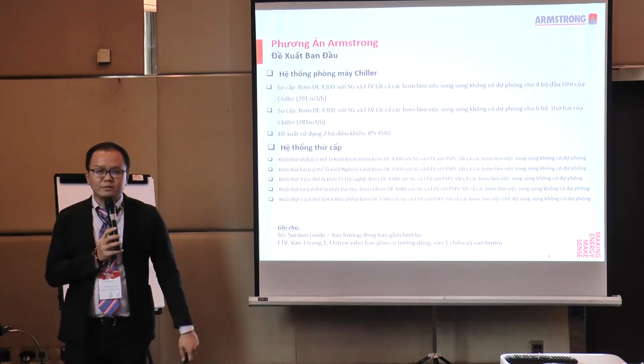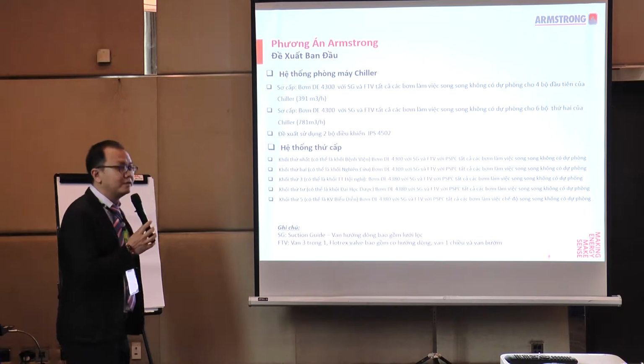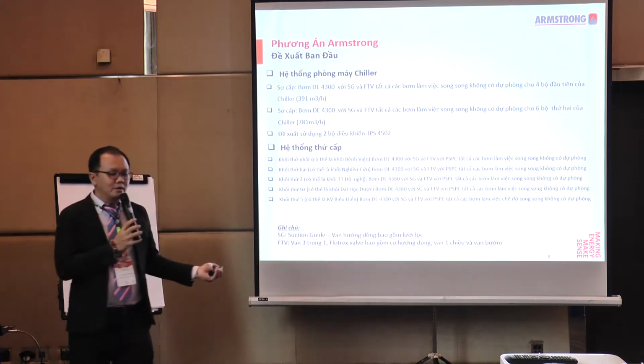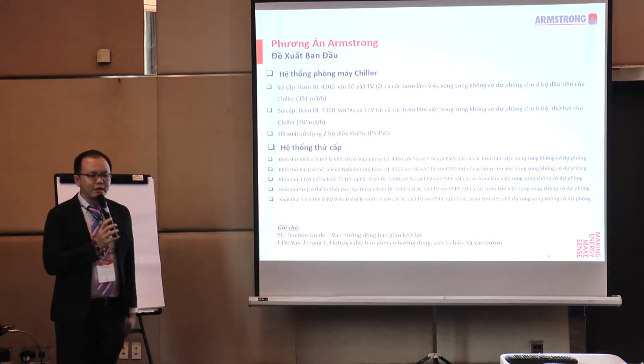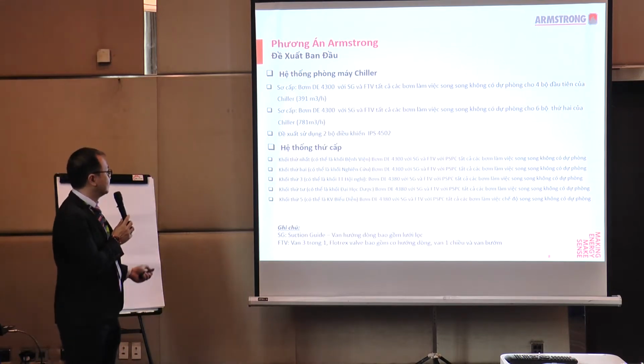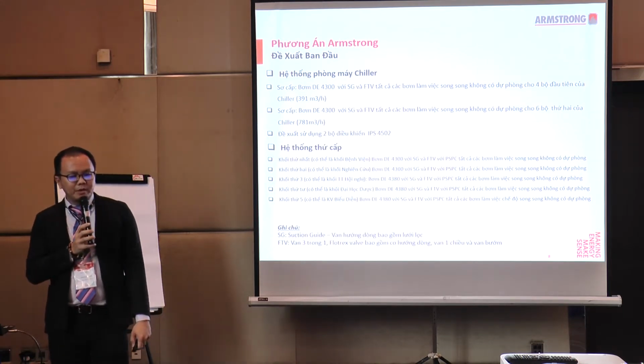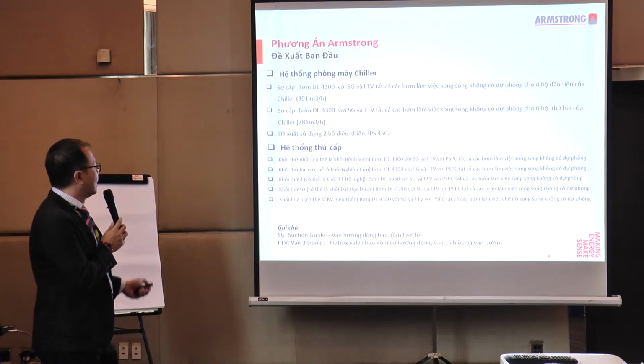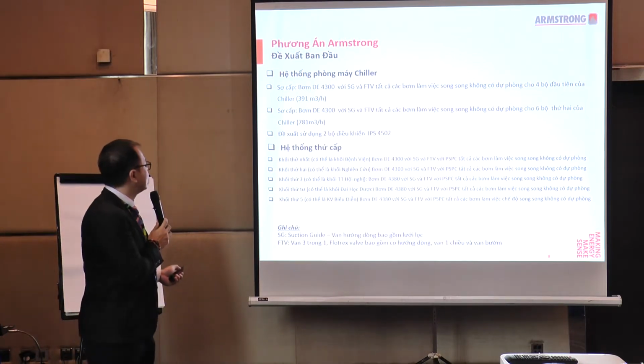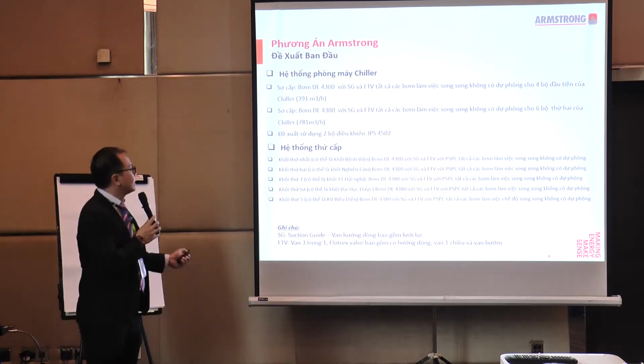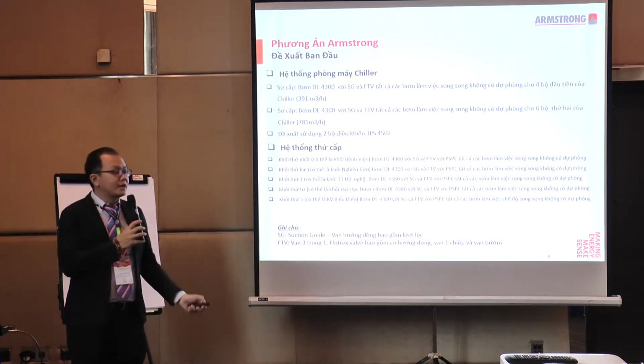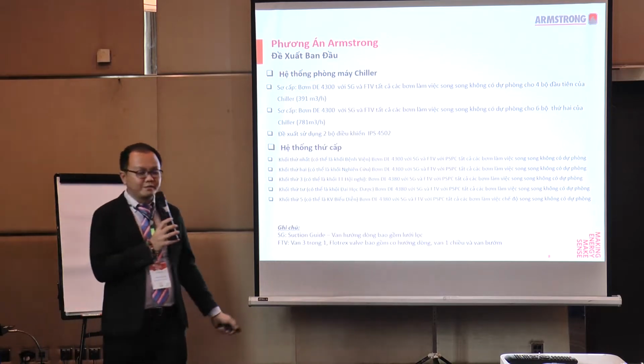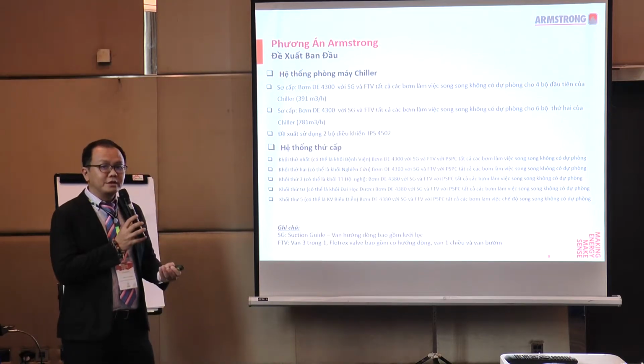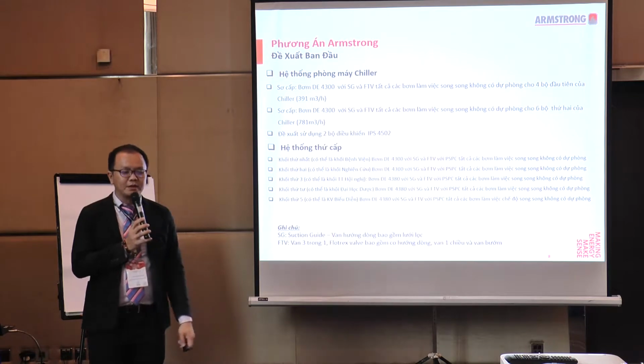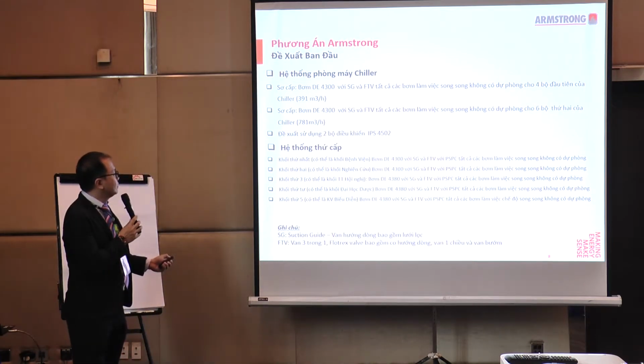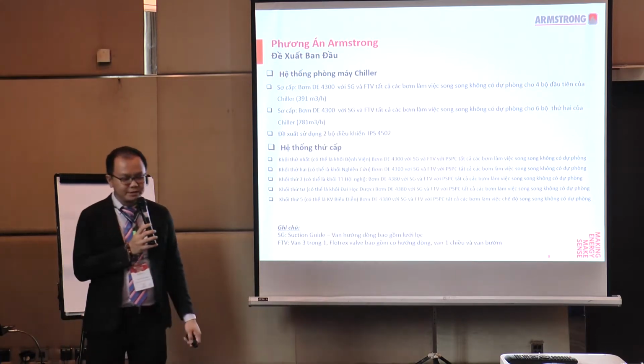So how does Armstrong come in? We actually have 2 different types of proposal. We started with this proposal for the chiller plant as well as the tertiary pumping systems. For the chiller pump, the primary systems, we propose the design envelope. This is the design envelope for the 200 series that we attach with our SG suction guide and FTV flo-trex valve. As you learned earlier, we designed this to be in parallel series, working for the 4 and also the 6 chillers.